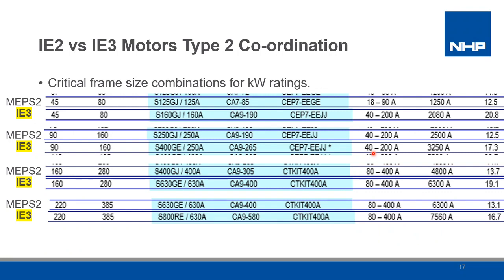Type 2 coordination tables for sites with MEPS or IE2 motors are available if required for existing switchboards, as the MCC cells may have limited space. As you can see, there are a number of starter sizes impacted with some IE3 kilowatt motor ratings. So with some frame break sizes, for a 90 kilowatt MEPS 2 motor you would utilize a 250 amp breaker frame, but with IE3 you would have to go to a 400 amp frame breaker, so the physical size is an issue, and this is occurring on a number of frame sizes of the breakers. New switchboards should be constructed based on IE3 premium efficiency motors.